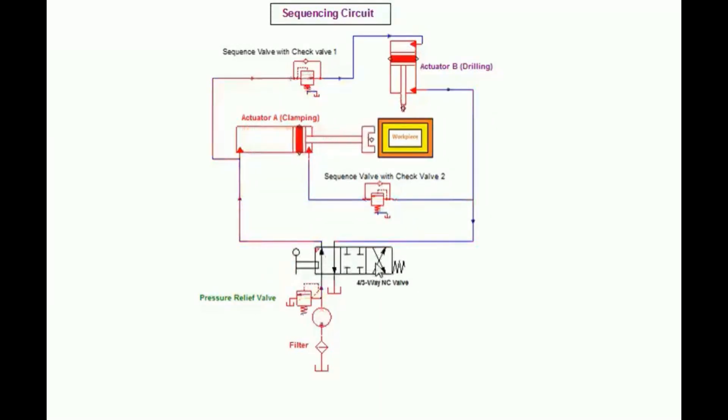When the third position is activating, cylinder B retracts first. After complete retraction of cylinder B, back pressure is built, so sequencing valve 2 opens and cylinder A retracts.